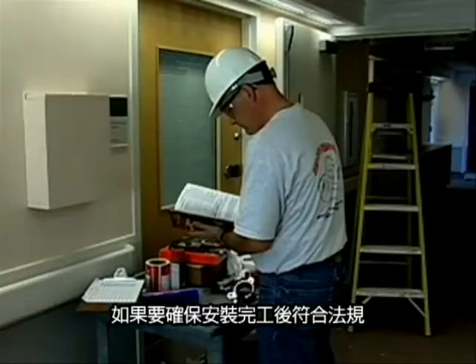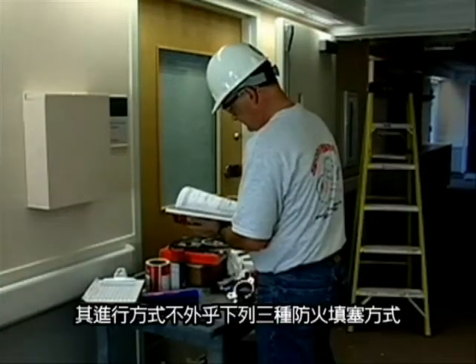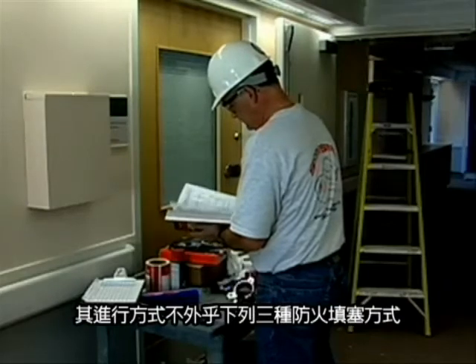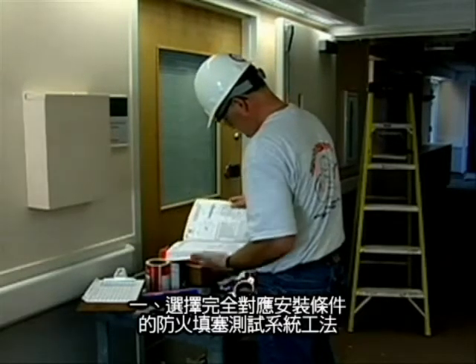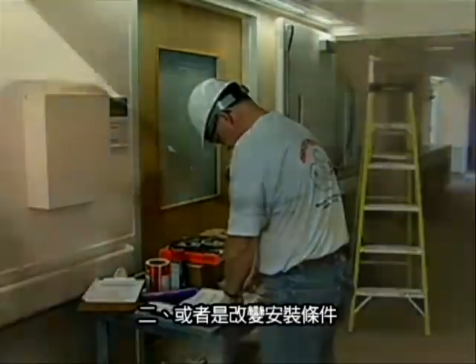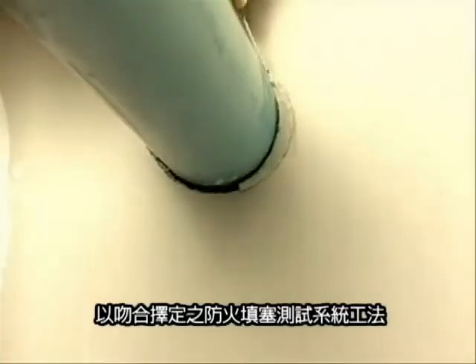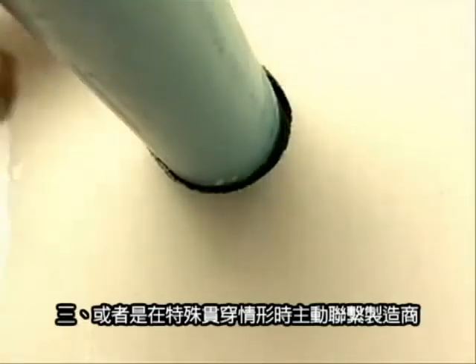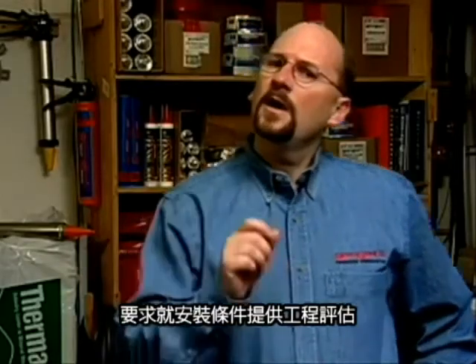If the installation is to be code compliant, an as-built condition must be fire stopped in one of 3 ways. Either choose a fire stop system that has coverage for your condition, or alter your as-built condition until it conforms to the requirements of a tested system. Or, in the case of unusual penetrations, you can contact the manufacturer and request an engineering judgment. The point is that no fire stop should ever be installed without a UL system or an engineering judgment to defend your work. And even then, great care is needed to ensure that the installation matches the system requirements precisely.